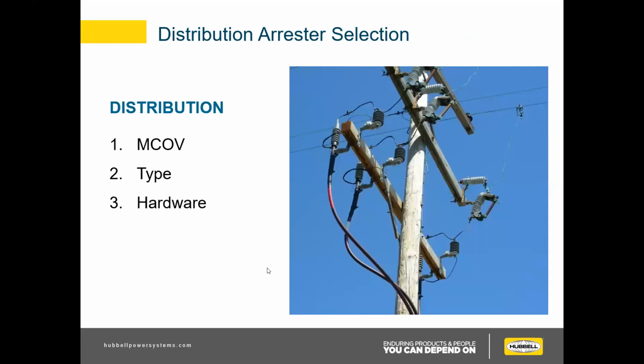The first thing we want to know if you ask us to provide you an arrestor part number is MCOV, which is calculated using your system voltage and grounding considerations. So you need to know your system voltage, and we'll need to know the type. If you have in mind that you want to use a heavy duty or a normal duty distribution arrestor, our PDV 65 is our normal duty, and our PDV 100 is our heavy duty, or riser pole application. We'll go over that more in a few minutes. It's a deeper topic.